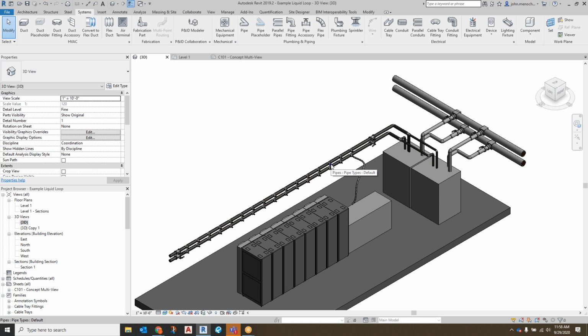One topic that came up earlier is there's a split here. We're dealing with the facility side, and initially people thought we're just talking that, but if there's no PDU or CDU, we're talking the piping down to the rack, so this is really all in scope for us. Sometimes this secondary loop is prescribed by the equipment manufacturer, and things like material compatibility, if it's a refrigerant or a dielectric or something else, that has to be specified by others. When it's general piping we can handle it, but when it's a proprietary fluid whose interactions we don't know, that has to be under the equipment manufacturer.